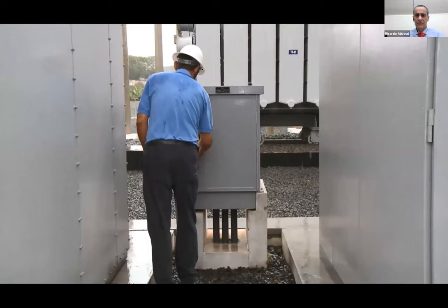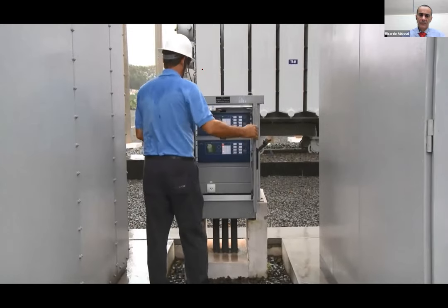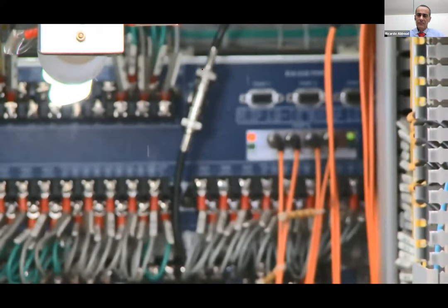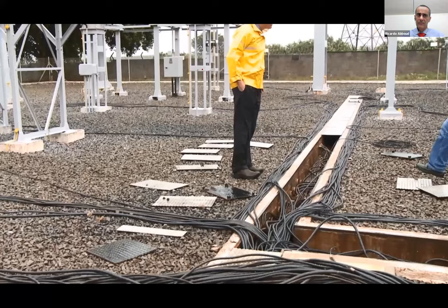The fact that SEL makes relays and Ethernet interfaces very rugged means we can move both out into the yard. And then we can move the information from the substation yard to the control building over a fiber optic cable using digital messages instead of bundles and bundles of copper conductors.